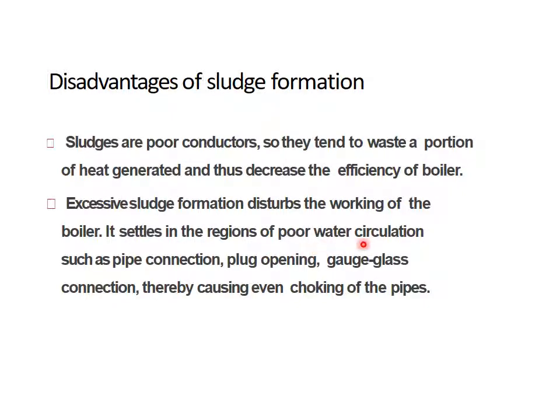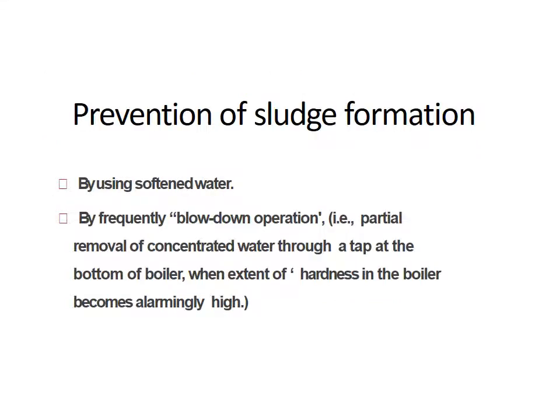Disadvantages of sludge formation: sludge is a poor conductor, so it tends to waste a portion of the heat generated and decreases the efficiency of the boiler. Excessive sludge formation disturbs the working of the boiler by settling in regions of poor water circulation such as pipe connections, plug openings, and gauge glass connections, causing blocking of the pipes.